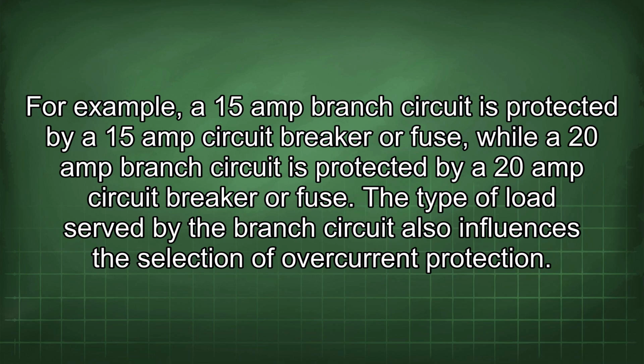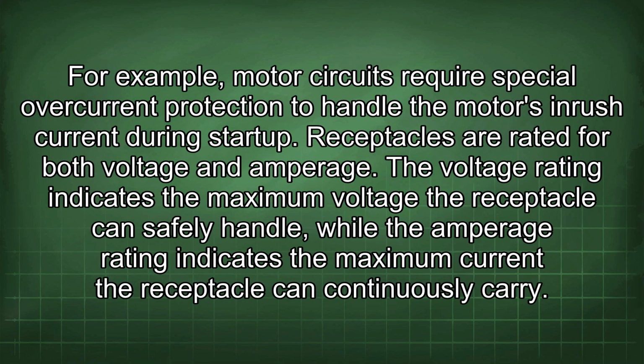The type of load served by the branch circuit also influences the selection of overcurrent protection. For example, motor circuits require special overcurrent protection to handle the motor's inrush current during startup. Receptacles are rated for both voltage and amperage. The voltage rating indicates the maximum voltage the receptacle can safely handle, while the amperage rating indicates the maximum current the receptacle can continuously carry.